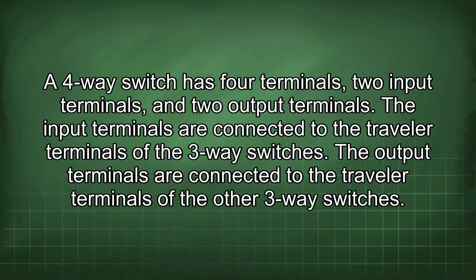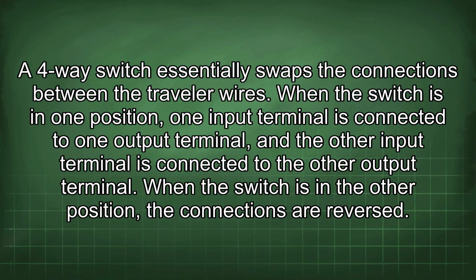A 4-way switch has 4 terminals: 2 input terminals and 2 output terminals. The input terminals are connected to the traveler terminals of the 3-way switches. The output terminals are connected to the traveler terminals of the other 3-way switches. A 4-way switch essentially swaps the connections between the traveler wires. When the switch is in one position, one input terminal is connected to one output terminal and the other input terminal is connected to the other output terminal. When the switch is in the other position, the connections are reversed.